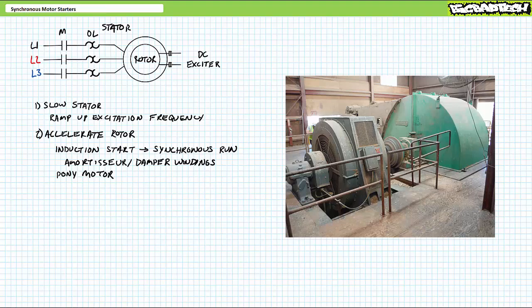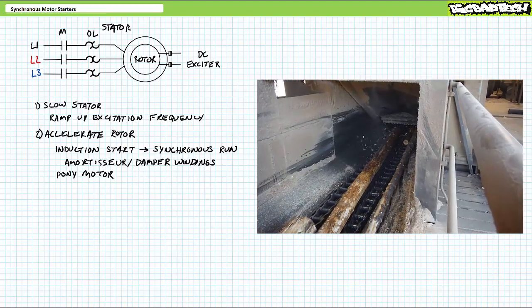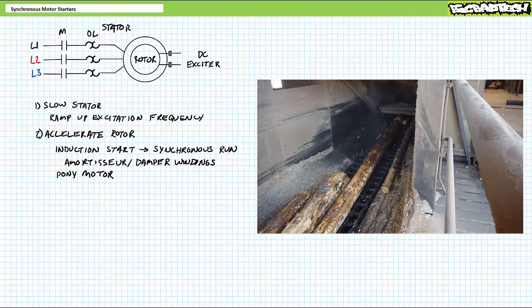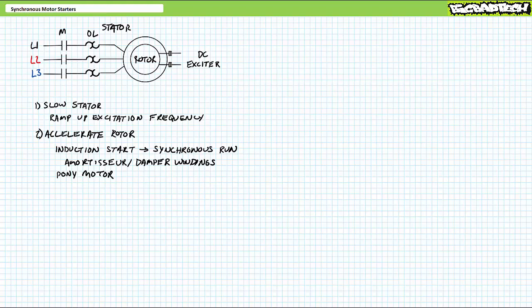At this time, the pony motor is de-energized, and the synchronous motor can then be put to work turning an entire Doug fir into a bag of bark chips, or whatever it's supposed to do. Long story short: stator and pony motor on, DC exciter off. When the rotor is close to synchronous speed, the stator stays on, but the pony motor and DC exciter perform a coordinated handoff to pony motor off and DC exciter on.